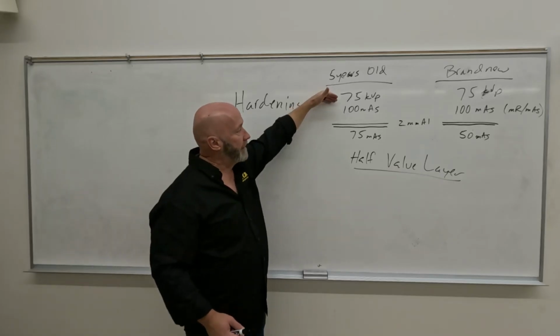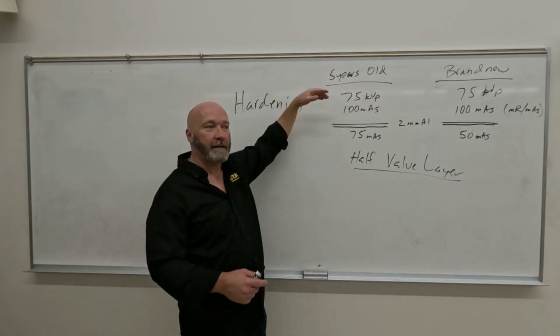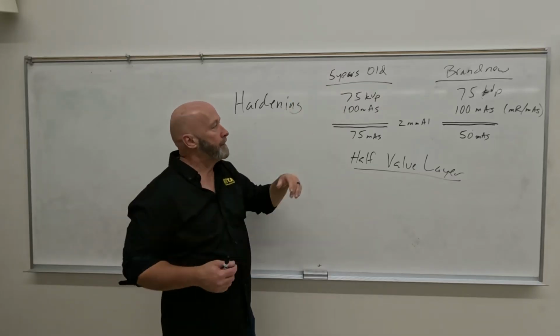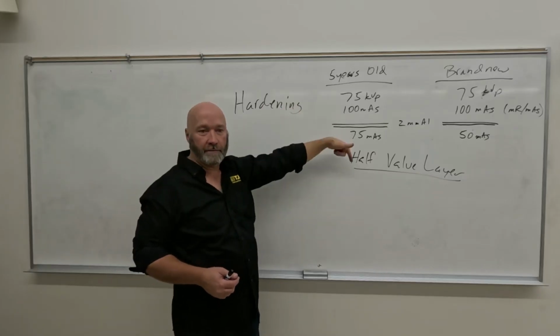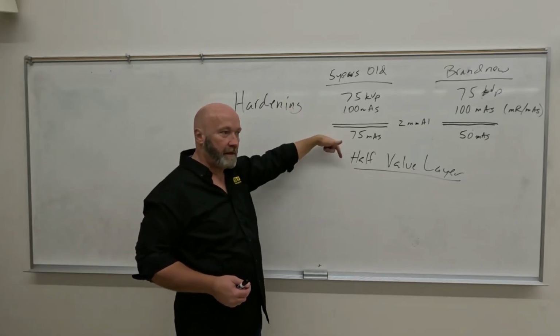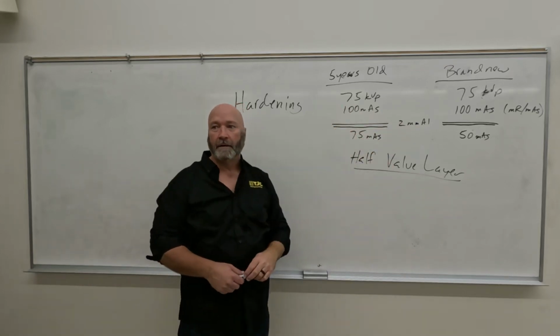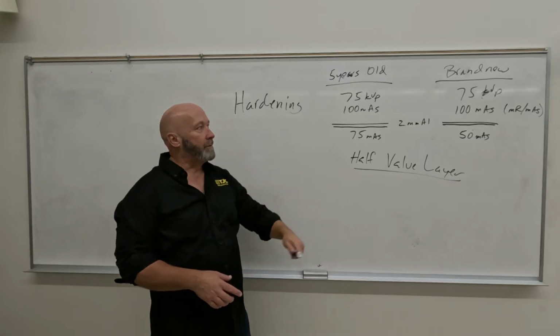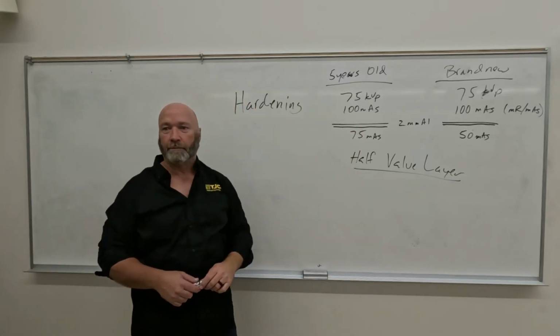But at 75 kVp, on this old, seemingly worn-out tube that they've had to adjust over the years, what's coming out of it is a harder x-ray beam that penetrates more, and therefore the x-ray beam is better out of this tube than that one. So why do we use brand new tubes? Why don't we just use all old x-ray tubes?